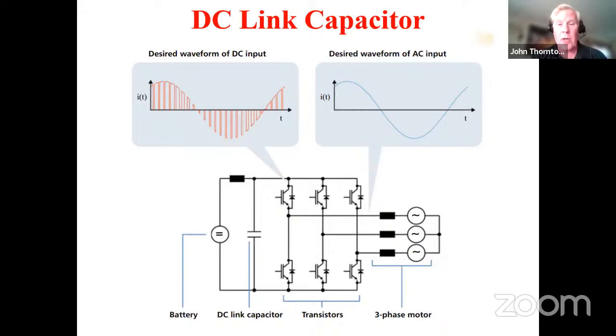So why they're critical inside of an inverter is this reason. In order to go from high voltage DC into high voltage AC, we have to make sure that the input voltage to these IGBTs is fairly stable. The controller inside of the inverter is going to switch the IGBTs in the correct order to generate a sine wave.